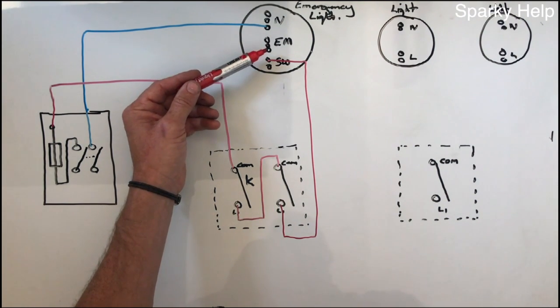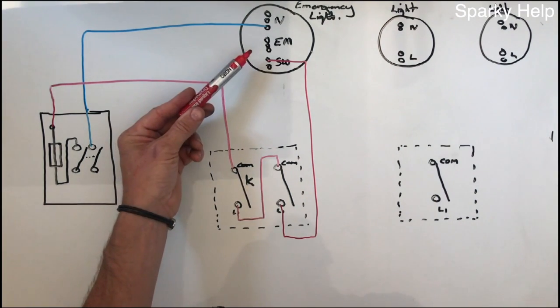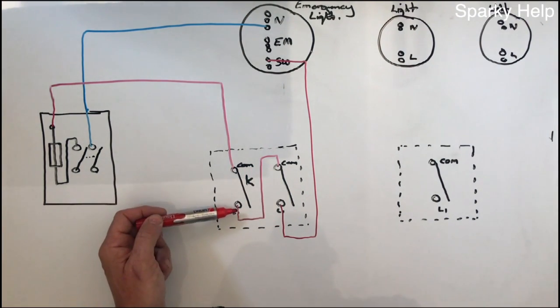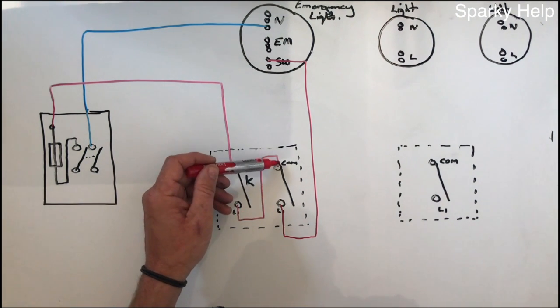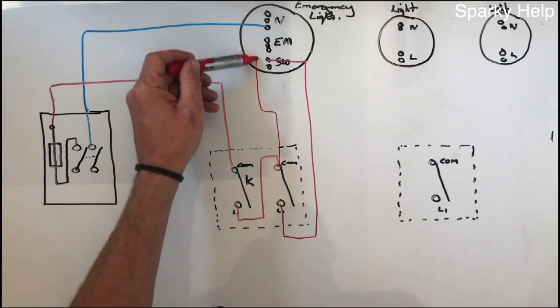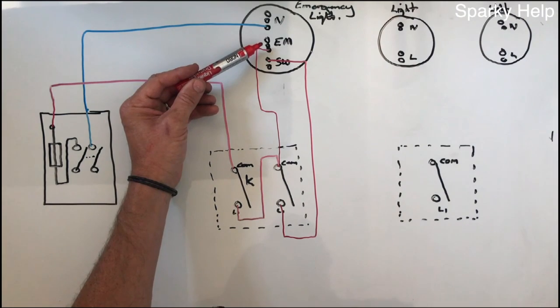But we need a permanent feed to the emergency light to feed the battery pack. But that's got to come from the key switch, so it can either come off of that point there, or that point there. It makes no odds, I'll come off of this one here. So it comes out and connects in there, and that becomes our permanent feed.